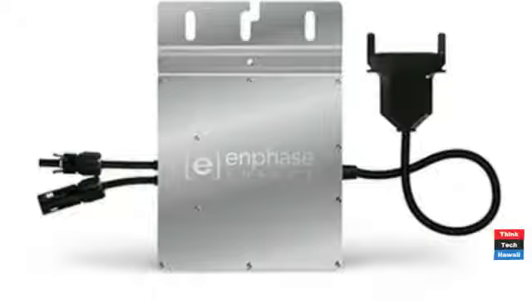I just wanted to ask you about the change of the firmware. Does your ability to change the firmware connect you to the microinverters, so that the microinverter needs signals from the internet in order to keep functioning, or is that just a software download, which is not necessary for the microinverter to work? The microinverter does not need any interconnection with our servers. It can work completely autonomously. In fact, it can perform some of what we call advanced grid functions, grid stabilizing functions, autonomously as well. There are benefits to being connected to the network. You can monitor and you can manage. But you don't need it in order to operate. No, absolutely, you don't need it.